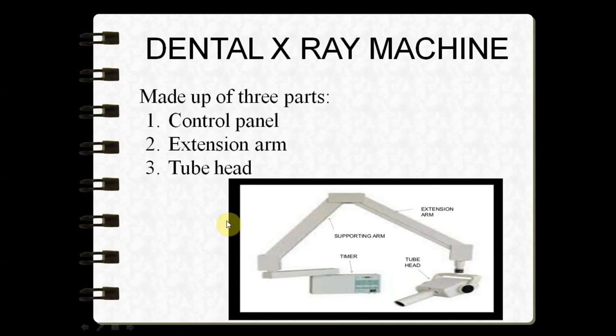The machine consists of a control panel, an extension arm, and a tube head. The control panel consists of an on/off switch, an indicator, an indicator light, and an exposure button. Once you press this exposure button, you can hear a noise, and once the noise fades off, it indicates that the exposure cycle has been completed.